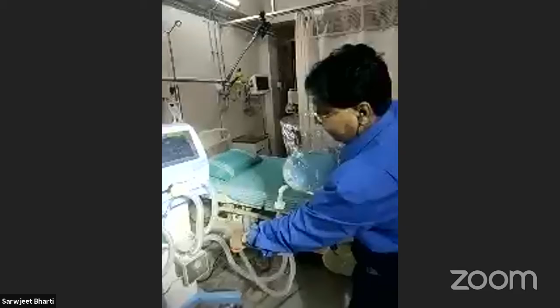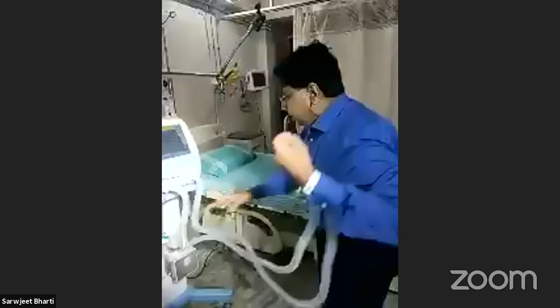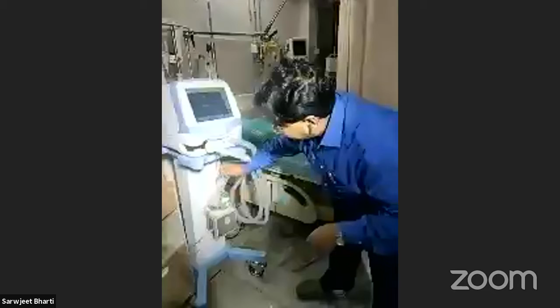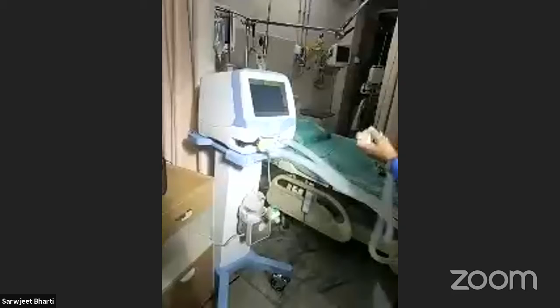Please understand that in case you are using a humidifying chamber with the oxygen in a ventilator, please attach this filter before the inlet of the ventilator into the humidifying chamber. Supposing this is the ventilator connection, you're using a humidification chamber so that you don't give just dry oxygen or dry ventilation to the patient. This is where we connect it. At that level, we always attach a viral filter here, and we don't put an HME filter there. We don't prefer putting it to the oxygen that is coming out of the ventilator if you're using a humidification chamber. Connect.